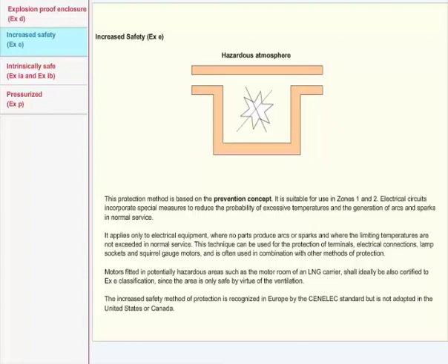Motors fitted in potentially hazardous areas such as the motor room of an LNG carrier shall also be ideally certified to Ex e classification, since the area is only safe by virtue of the ventilation. The increased safety method of protection is recognized in Europe by the CENELEC standard but is not adopted in the United States or Canada.